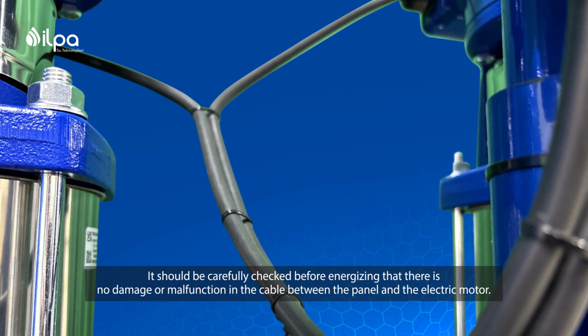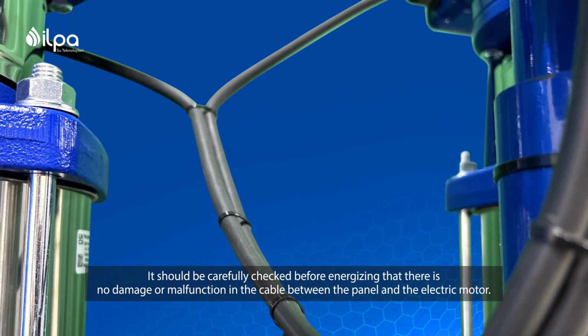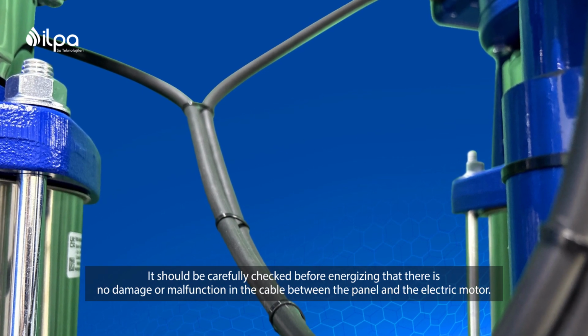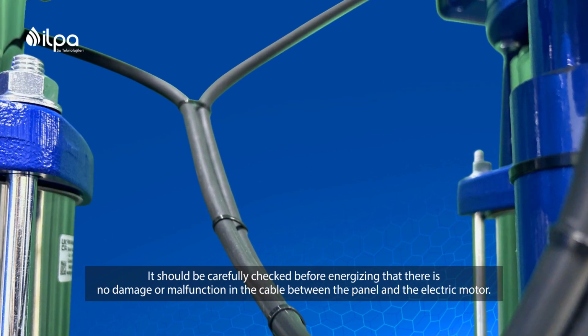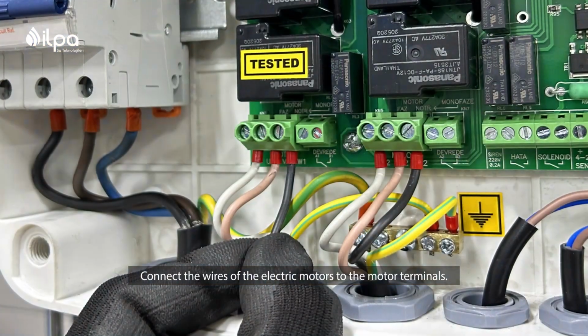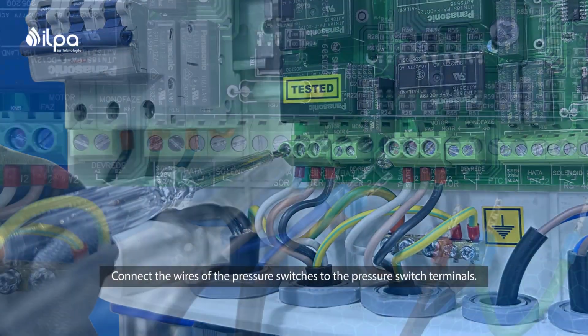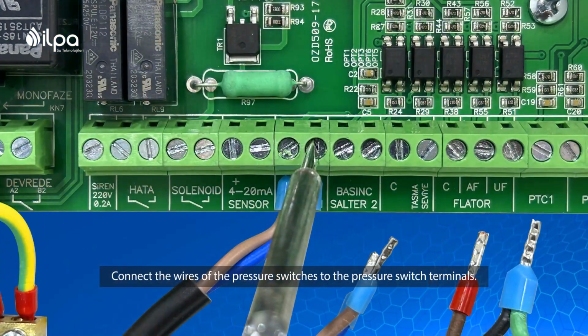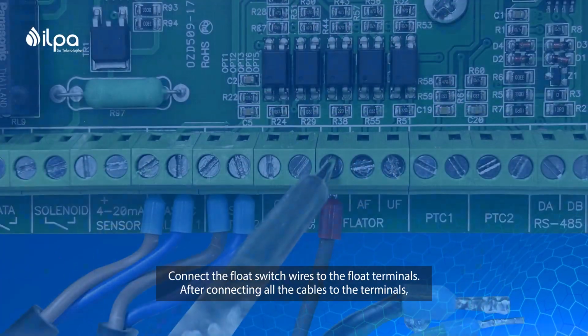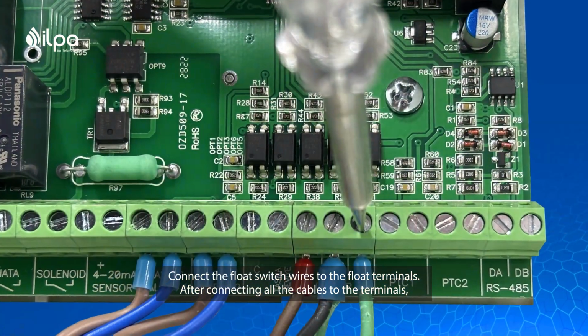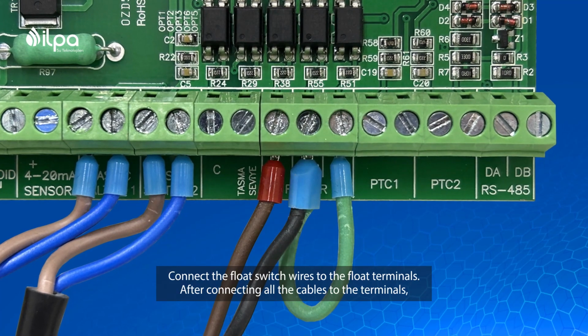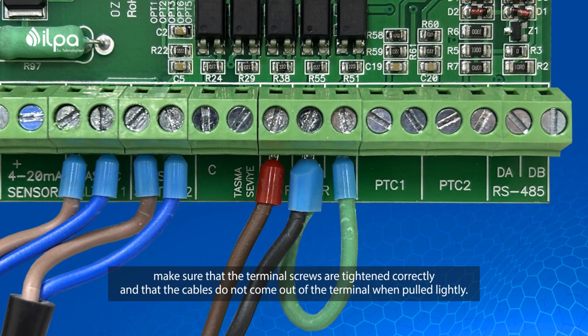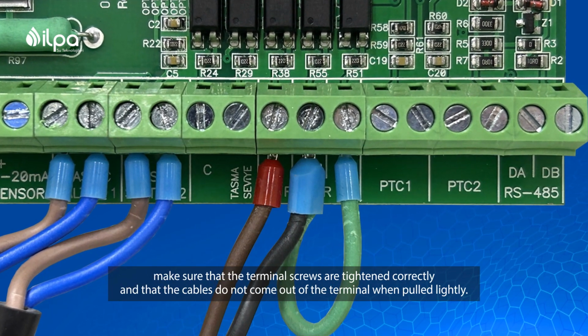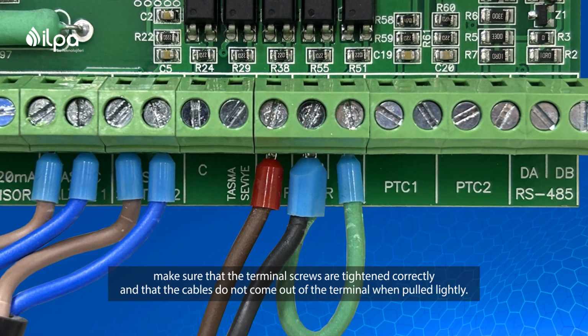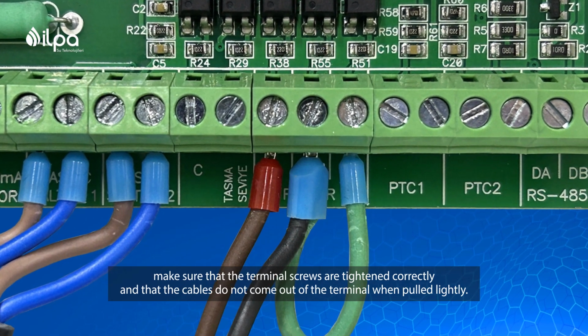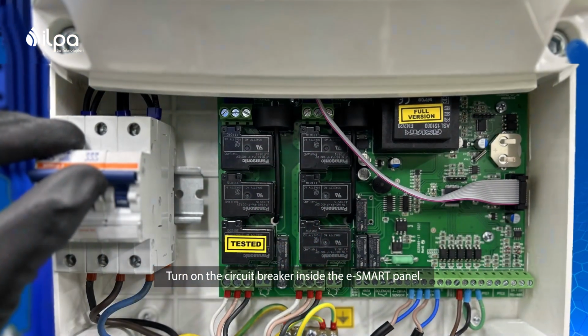It should be carefully checked before energizing that there is no damage or malfunction in the cable between the panel and the electric motor. Connect the wires of the electric motors to the motor terminals. Connect the wires of the pressure switches to the pressure switch terminals. Connect the float switch wires to the float terminals. After connecting all the cables to the terminals, make sure that the terminal screws are tightened correctly and that the cables do not come out of the terminal when pulled lightly. Turn on the circuit breaker inside the eSmart panel.